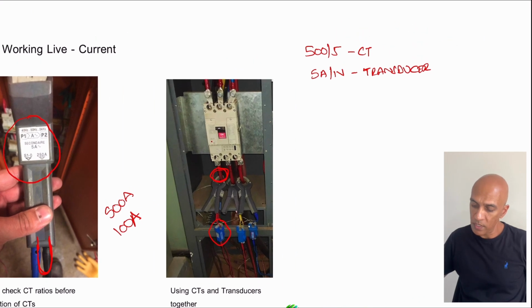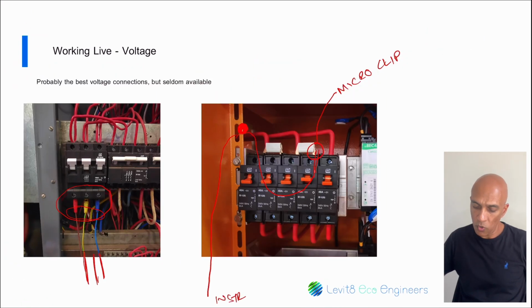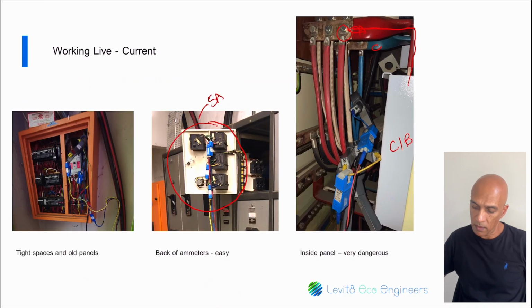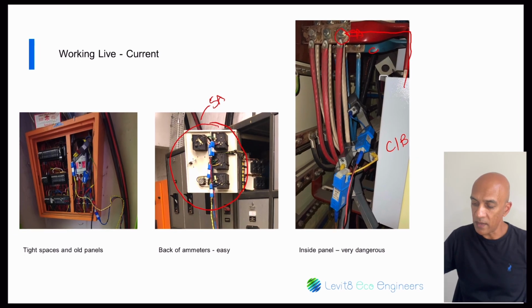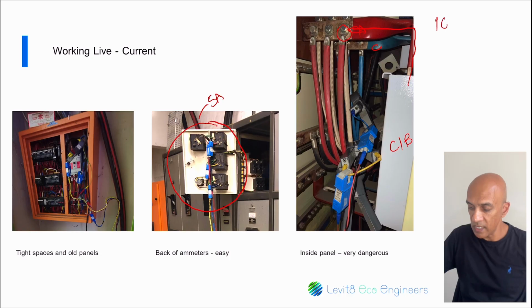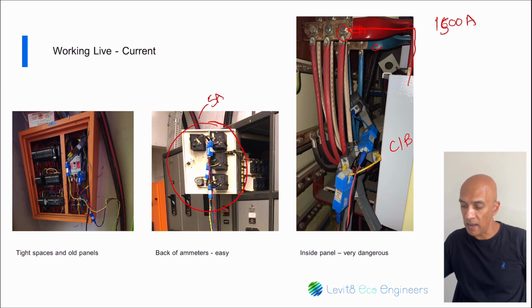Now another very important thing to remember. Let us go back 2 slides. Let us go back to this slide. Now if you have a look here, we have multiple cables that are going out on a single feeder, on a single phase rather. Now what happens in this case? The rating of the breaker might be too high. Let's assume it is 1,600 or 1,500 amps. Now that's way more than what a single cable can carry. So we're going to be using multiple cables here.